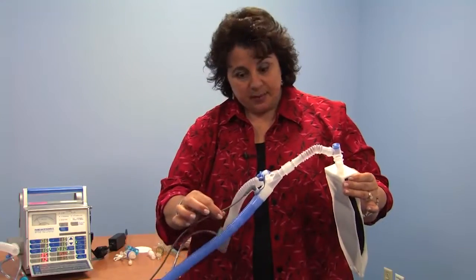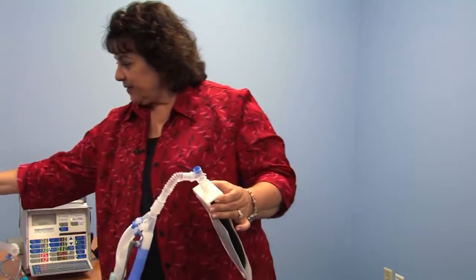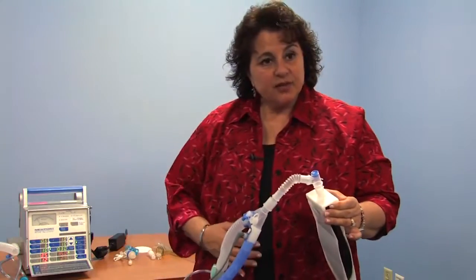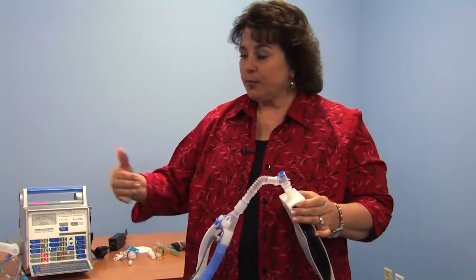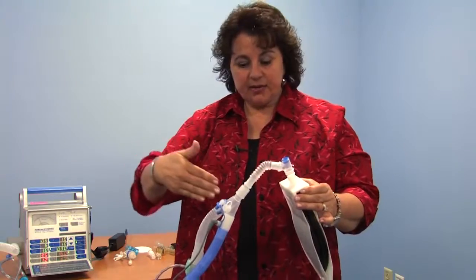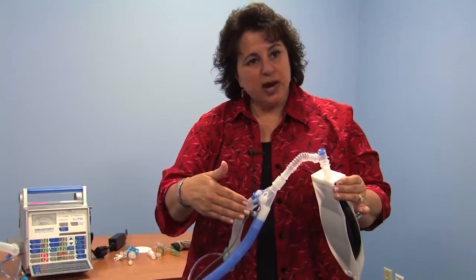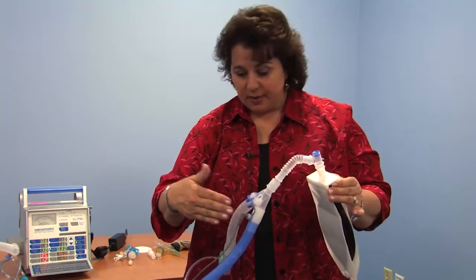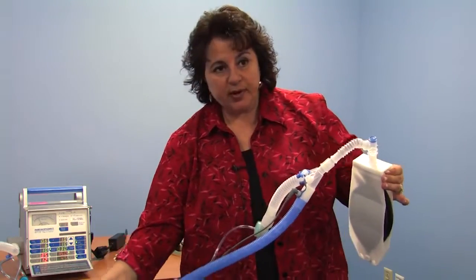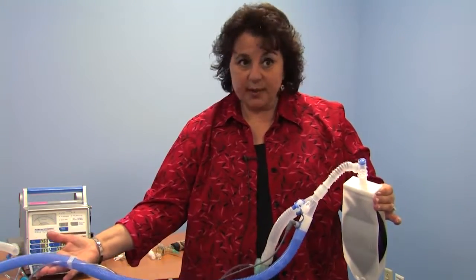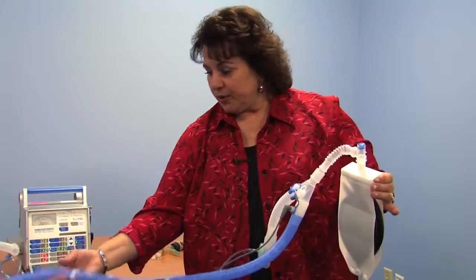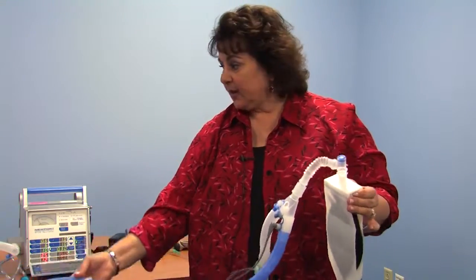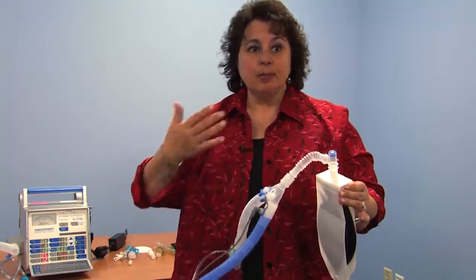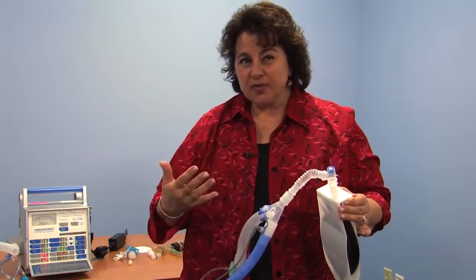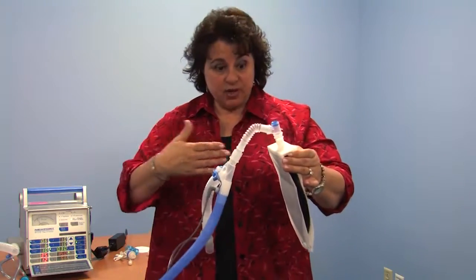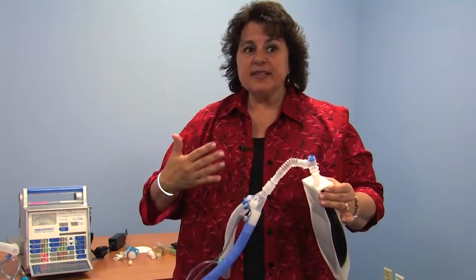You'll see we have some permanent wires here and adapters into the circuitry. That allows the humidifier to look at temperature both coming out of it and the air temperature up near your child. This is where we've prescribed we would like near body temperature here. So this is the tubing that you want to be aware of, to have condensate but not puddling of water. We don't want puddling to shake it and cause the machine to do false breath initiations, or what we call auto-cycling, because it will give the child breaths and potentially hyperventilate them.